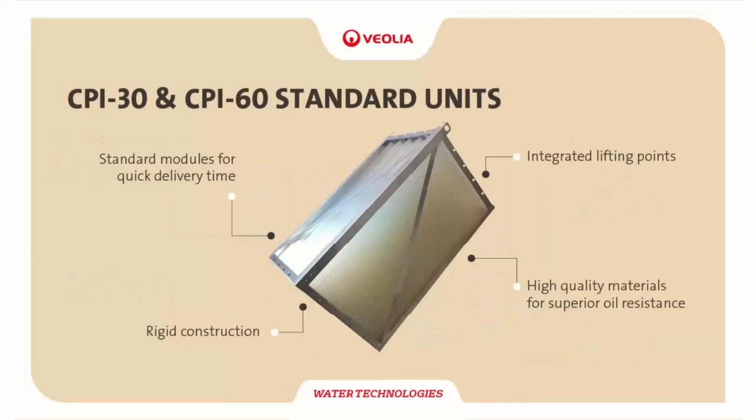When we zoom in on the internals, this is one of the plate packs. You can see the frame. It's a 316 frame. We see that the construction is relatively easy, but also compact and robust. And we see the plates inside, the corrugated plates. Because of its shape, corrugated gives more mechanical strength, and the material is chosen to have this high resistance to oil materials. There are integrated lifting lugs, so you can hoist it out for cleaning if needed, and you can place it back very easily. It's not clamped, it's not screwed, so you don't have to unbolt it. It's just lying there doing its work in the CPI tank.